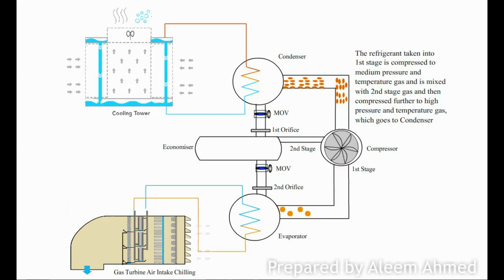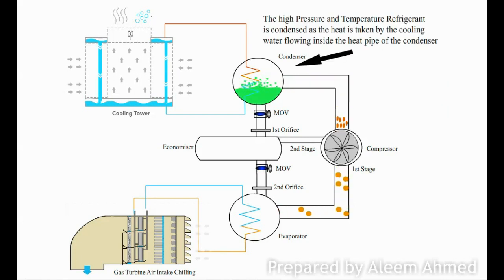The gas is then mixed with economizer gas and goes to the second stage of the compressor, which further increases the pressure and temperature. The high pressure and temperature refrigerant gas is then condensed in the condenser, in which cooling tower water circulates to take away heat from the hot refrigerant gas.